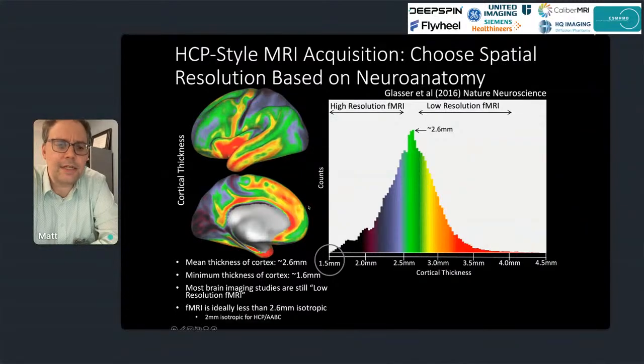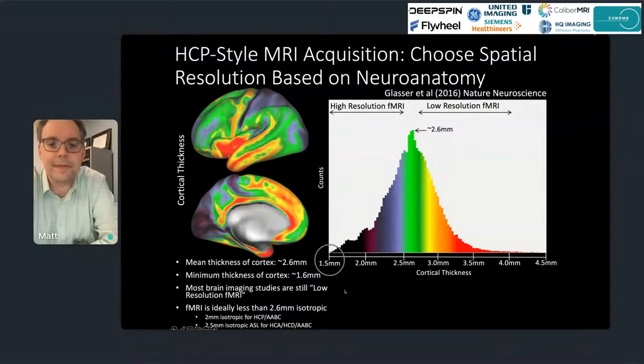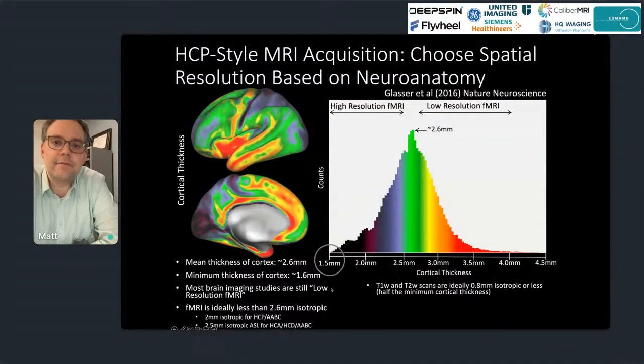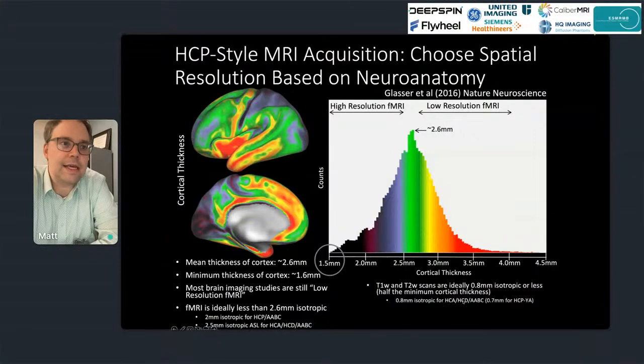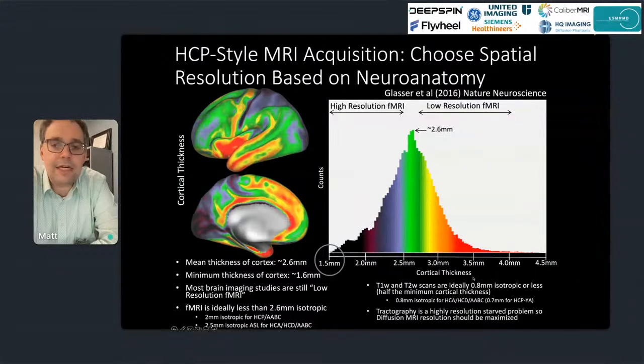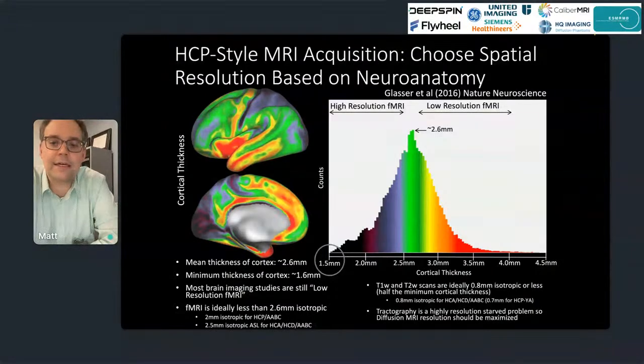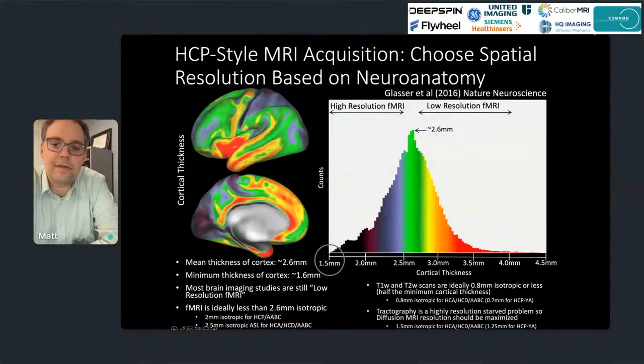For high-resolution 3D structural scans — T1-weighted and T2-weighted images — we ideally want 0.8 mm isotropic or less, which is basically half the minimum cortical thickness of 1.6 mm. That helps ensure we can make accurate cortical surface models even in the thinnest cortex. We used 0.8 mm for the HCP lifespan projects and 0.7 mm for the young adult HCP. For tractography, voxel resolution is always much coarser than actual axons, so we should maximize diffusion resolution — 1.5 mm isotropic for lifespan and 1.25 mm for young adult HCP.